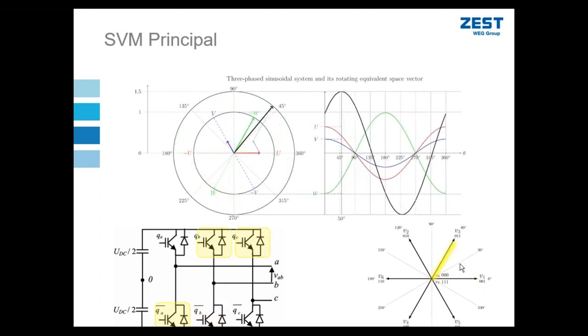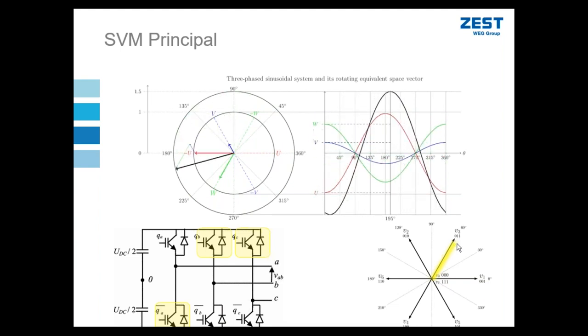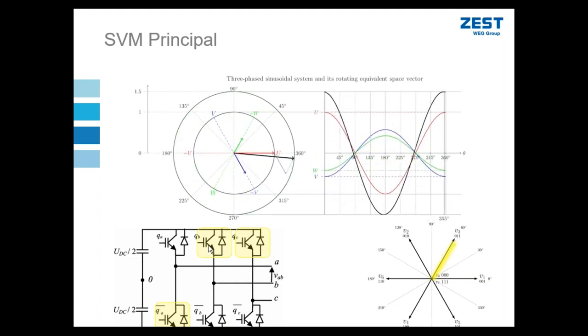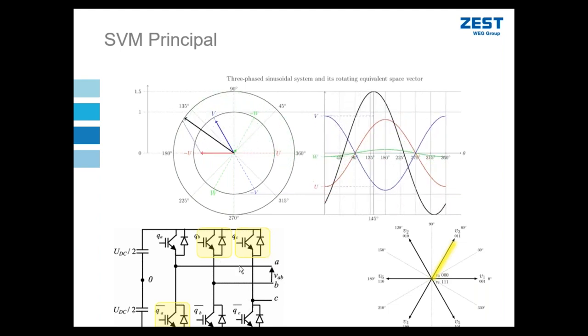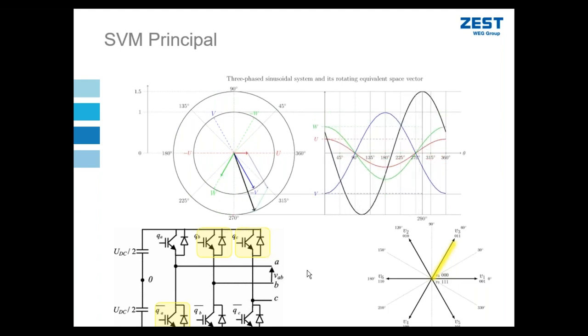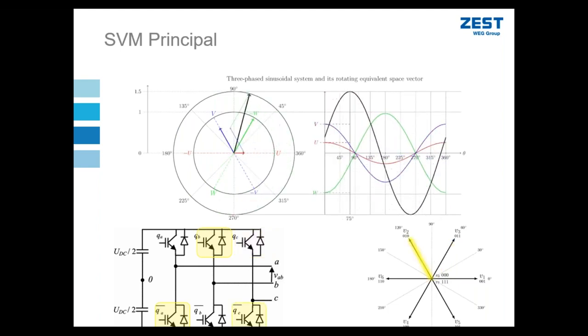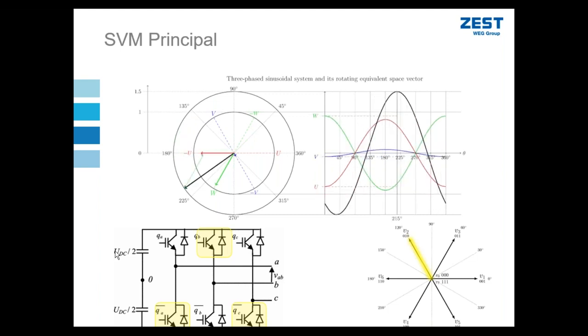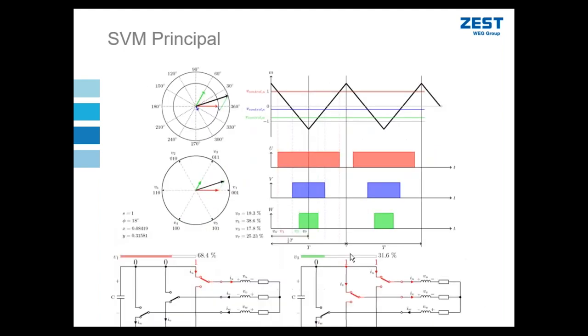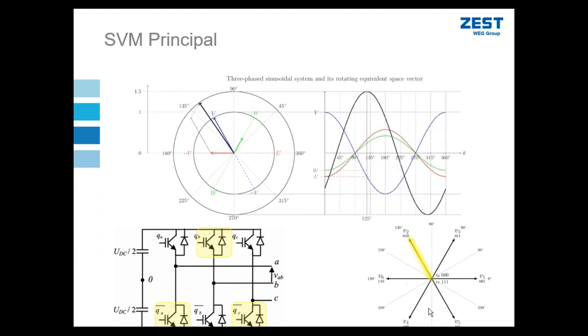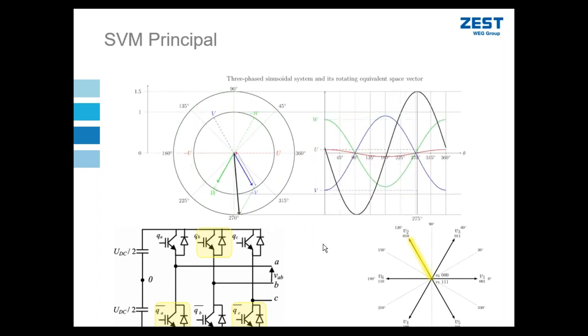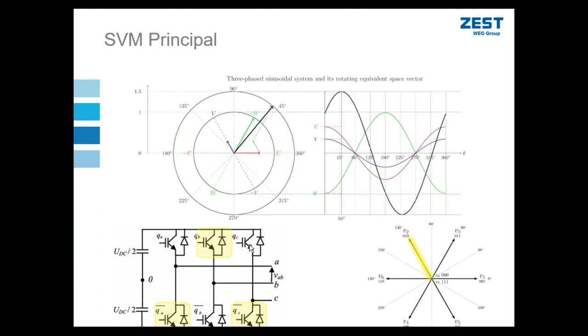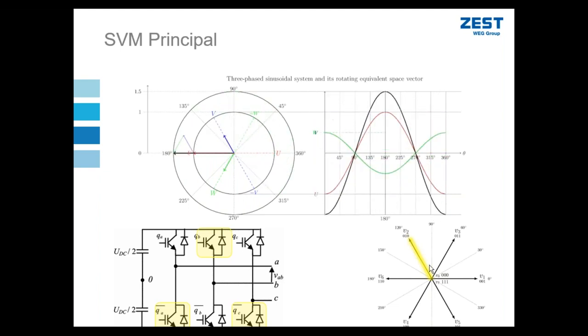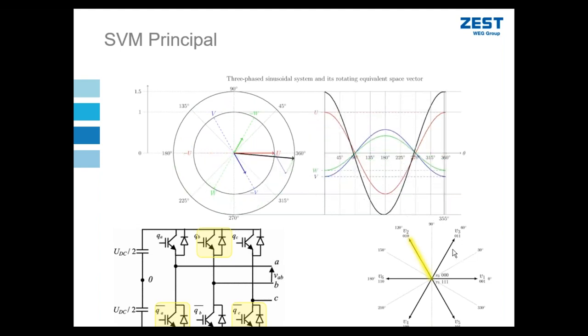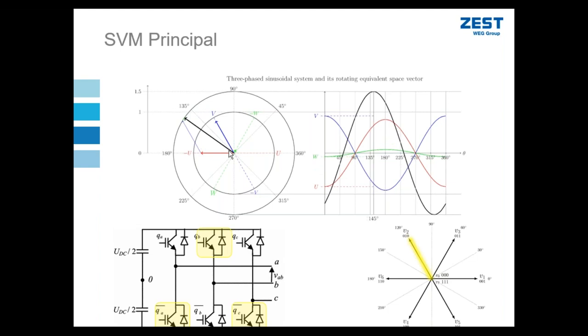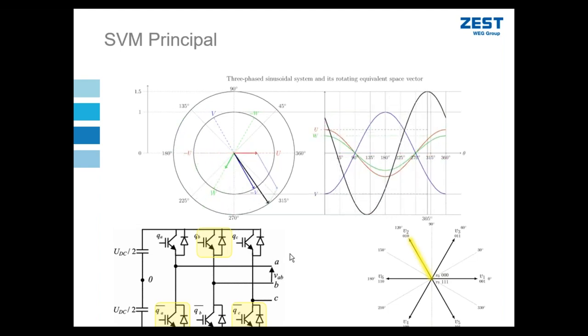I can then transition to vector 3 by switching 0, 1, 1. IGBT 1 is at 0, IGBT 2 is at 1, so in other words it's switching, IGBT 3 at 1. Vector V2 is 0, 1, 0 on the top, it's displayed there. And so we can continue and provide any of those 8 vectors through different switching options. I then need to switch a combination of any 2 vectors to enable me to get to 1 single rotating vector.